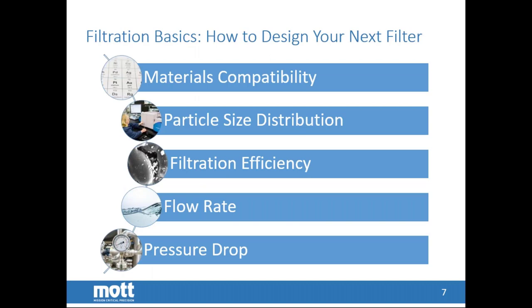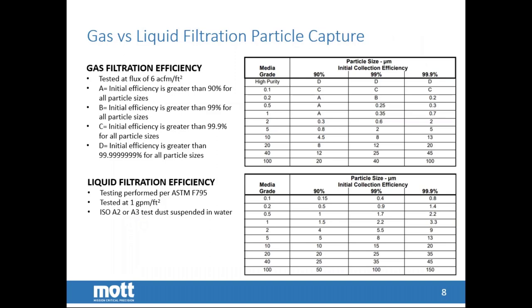We have a broad range of experience in designing filter products for many different industries. These are five of the key components that we look at when we do designs. We want to make sure our filters are compatible with the material that is flowing through them. We like to know what kind of particle capture size distribution you're looking for and what kind of efficiency you're looking for to capture those particles. And obviously, the flow rate of the fluid, either liquid or gas, and some idea of what your allowable pressure drop requirements are.